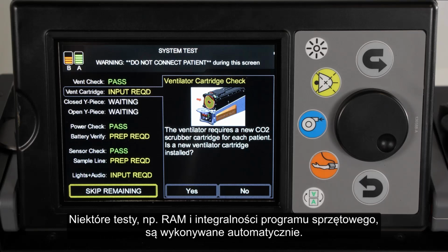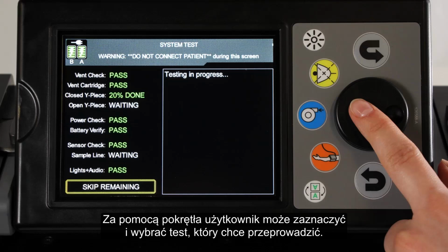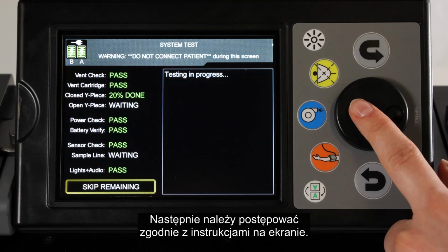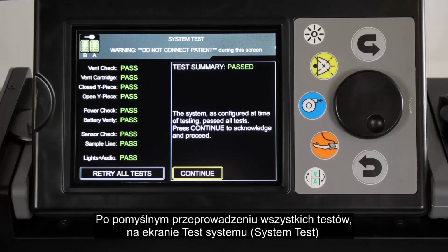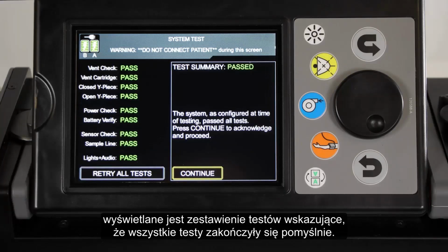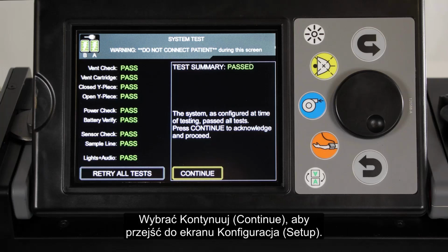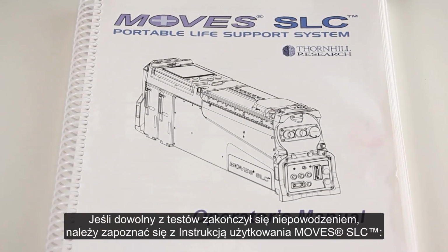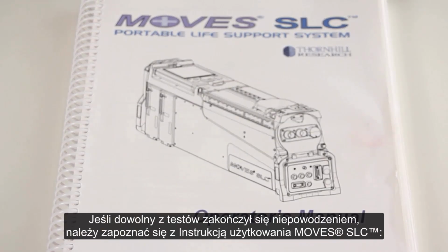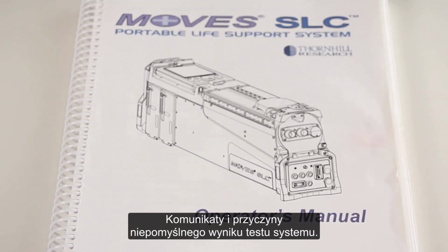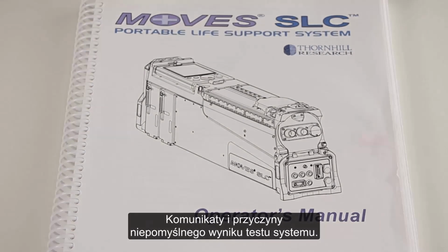Some tests, including RAM and firmware integrity, are automatic. Using the jog wheel, highlight and select the test which you would like to run and follow the instructions on screen. If all tests are successful, the system test screen displays a test summary indicating all tests have passed. Select Continue to move on to the setup screen. If any individual test fails, please refer to the Moves SLC Operator's Manual, System Test Failure Messages and Causes.